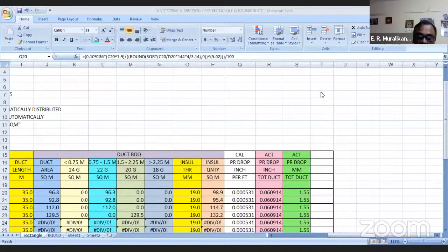So return air will definitely pick up some condensation or heat load. So the mass of air will be slightly higher if at all it picks up some moisture. Only the mass of air is important. If the velocity is increased by 1000 fpm to 1200 fpm, the duct size will go a little bigger. But technically, there is no advantage or disadvantage except for cost, if at all the size goes one size higher. Instead of 22 gauge or 24 gauge, that may be a factor in cost. Otherwise, technically, for a small delta increase or decrease in CFM, the duct aspect ratio and length doesn't go very high. You can see for yourself, a few fractions don't matter. So I can have the same supply and return, no issues.